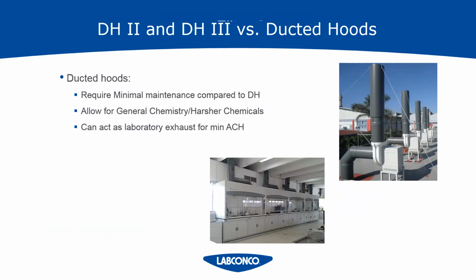So also with a ducted hood, the user can be a little more lenient with the chemicals used. You don't have to worry about filling up filters or not being able to use the chemicals in a ducted hood. The worst that can really happen is you can corrode your fume hood liner and you'd have to replace it, but that won't happen overnight. You'd have plenty of warning before that would need to happen. So you wouldn't have to worry about your filter having breakthrough and possibly stopping the work before it's complete. So as long as the blower is going on the ducted hood, the fume hood is going to be doing its job.